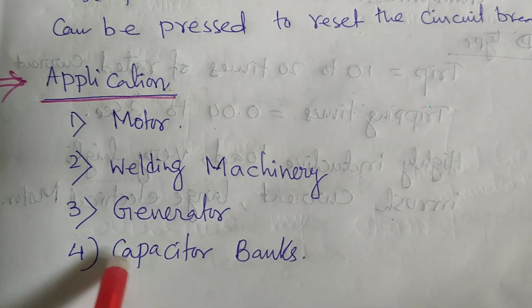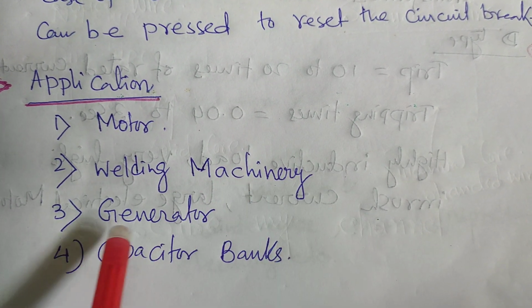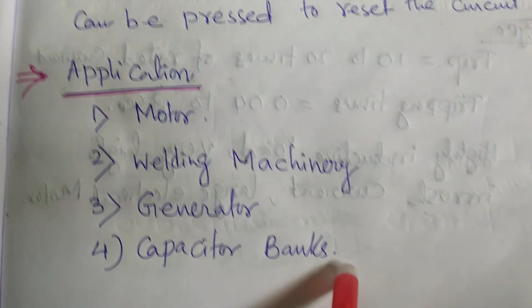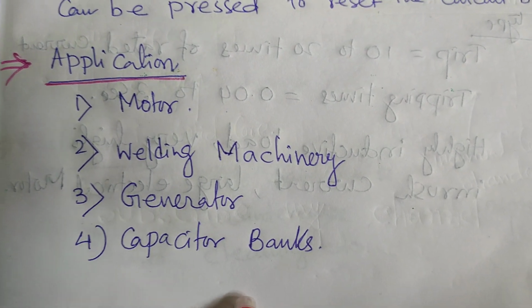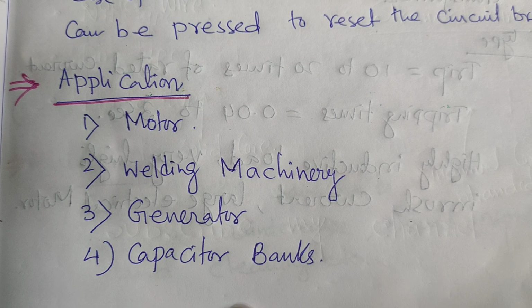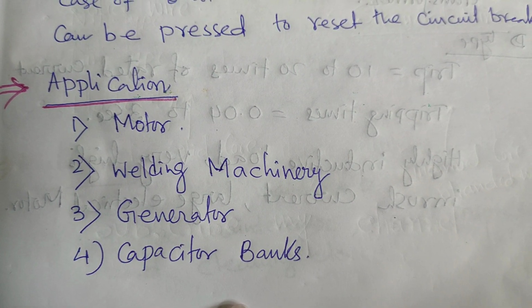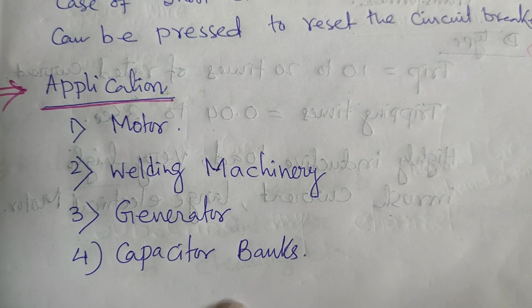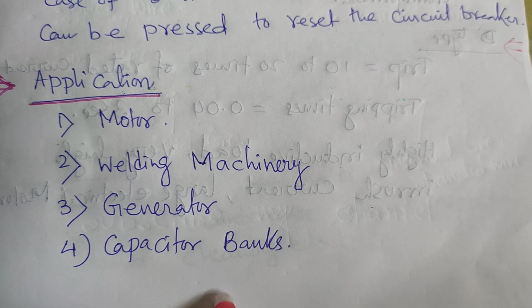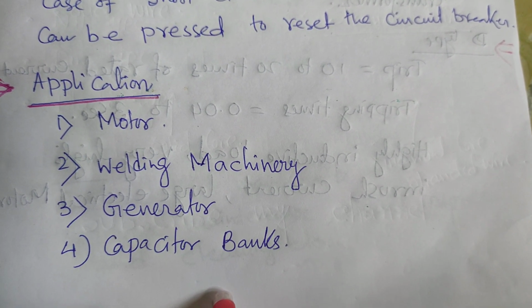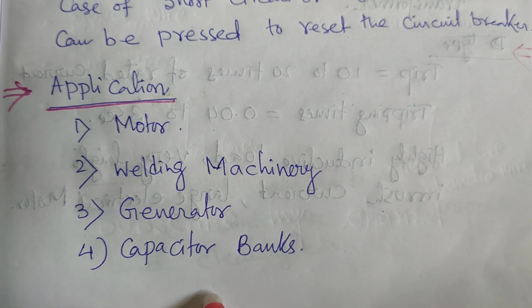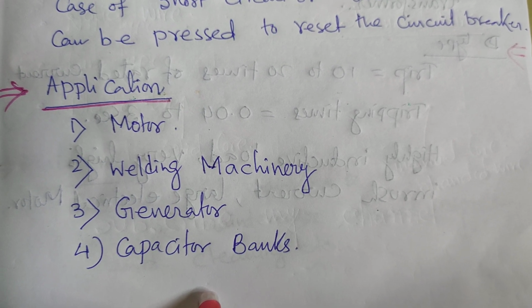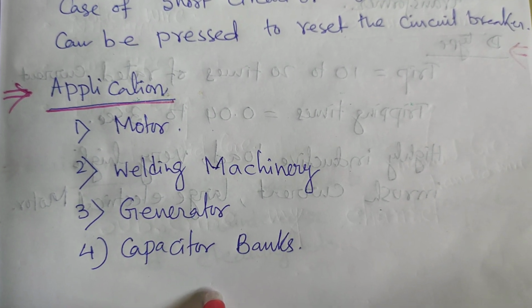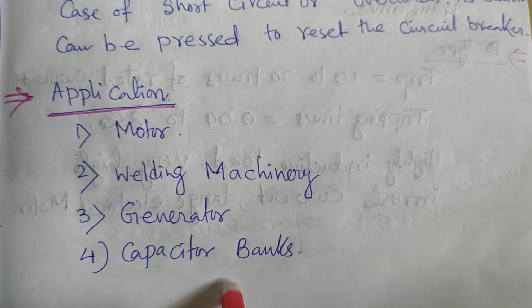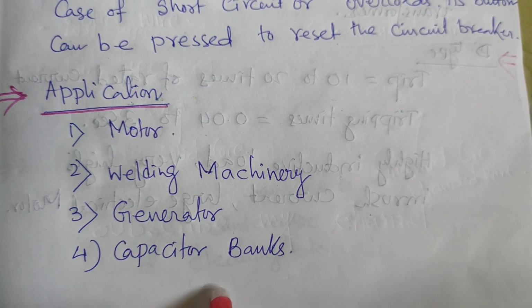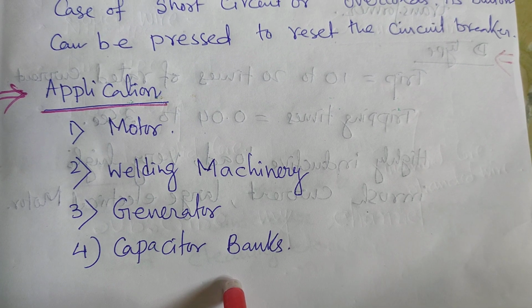Applications: where we use the MCCB. In the motor circuit, the welding machine circuit, the generator circuit, the capacitor bank circuit, inside the substations and power plants. We are using it inside the ACDB, and from the ACDB we provide power to different areas, different DBs. For example, for illumination purposes we provide 100 ampere, or 63, or 32, as per your illumination lamps. So in the substations we have different ampere ratings of MCCB connected in parallel for different purposes. One is for illumination, one for battery supply, one for motors, one for the filter machine, one for the transformer, one for the breaker.